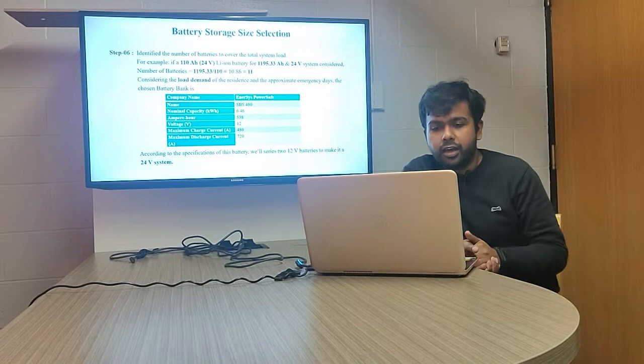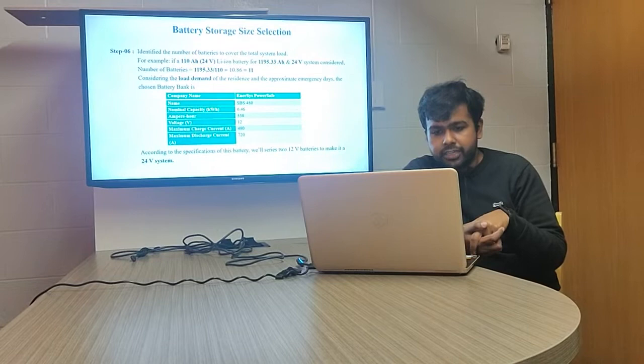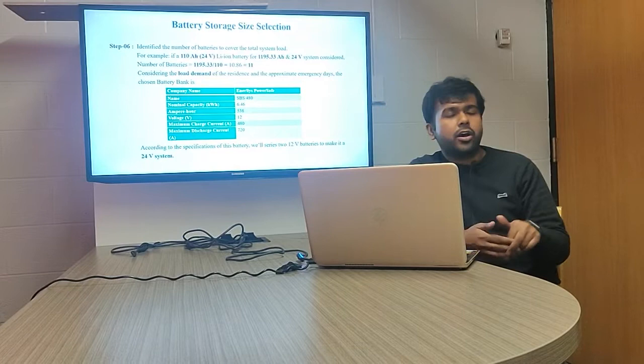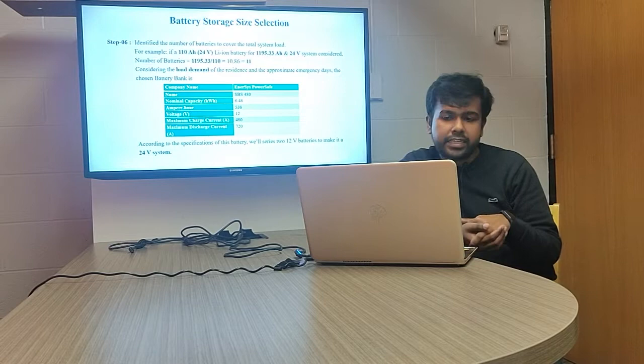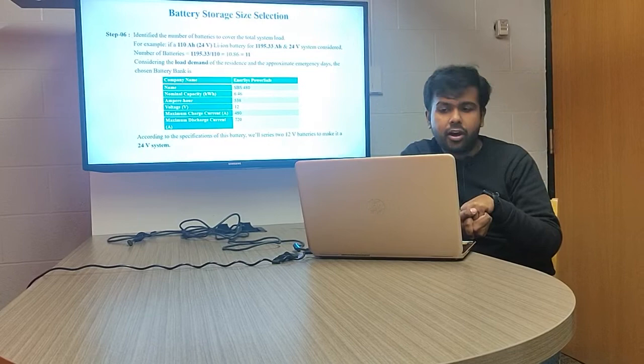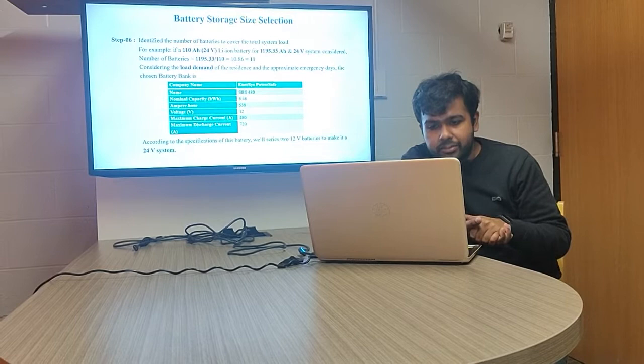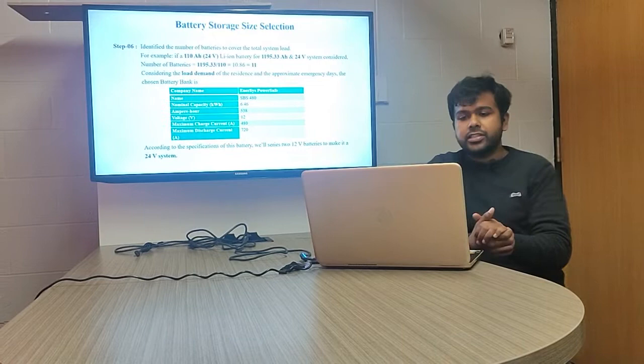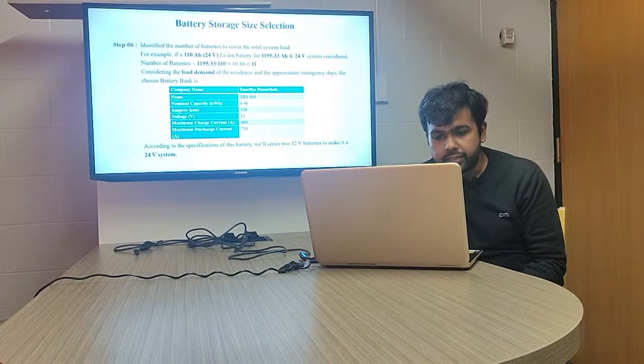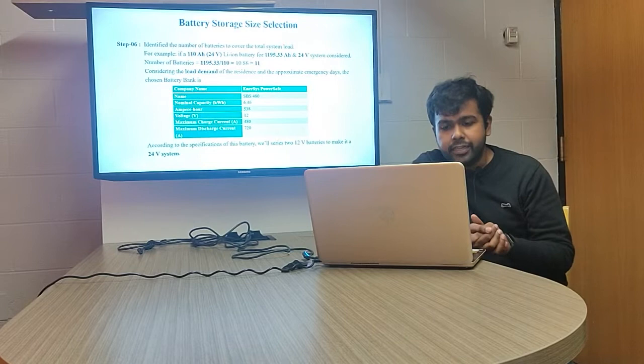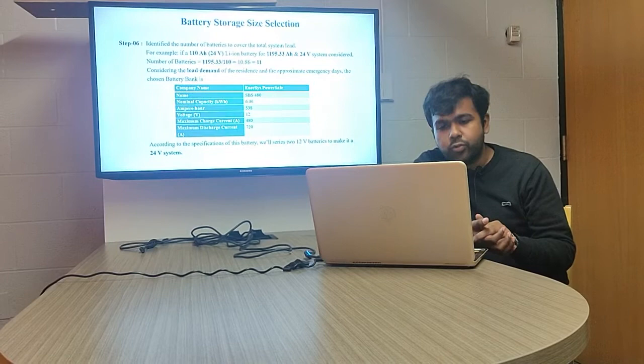In this slide, we show an example of selecting the number of batteries for our project. If we consider a 110 Ah battery of 24 volts, with our total requirement of 1195.33 Ah at 24 volts, we would need 11 batteries. However, based on real-life considerations, we selected the SPS 480 battery, which has a capacity of 6.846 kilowatt-hours and 538 ampere-hours. It is a 12-volt battery, so for our 24-volt system we considered two of these batteries.